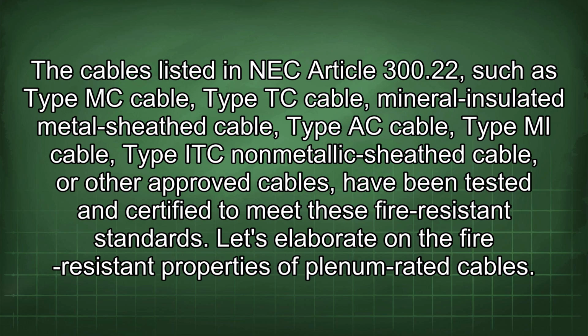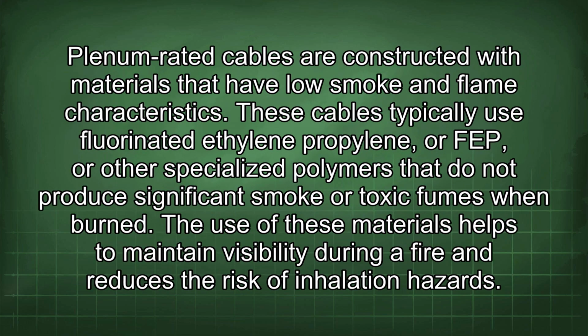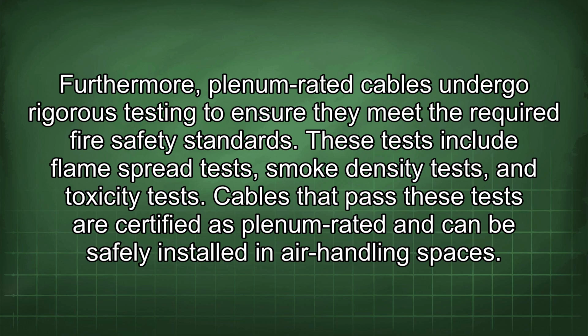Let's elaborate on the fire-resistant properties of plenum-rated cables. Plenum-rated cables are constructed with materials that have low smoke and flame characteristics. These cables typically use fluorinated ethylene propylene, or FEP, or other specialized polymers that do not produce significant smoke or toxic fumes when burned. The use of these materials helps to maintain visibility during a fire and reduces the risk of inhalation hazards. Furthermore, plenum-rated cables undergo rigorous testing to ensure they meet the required fire safety standards. These tests include flame spread tests, smoke density tests, and toxicity tests. Cables that pass these tests are certified as plenum rated and can be safely installed in air handling spaces.